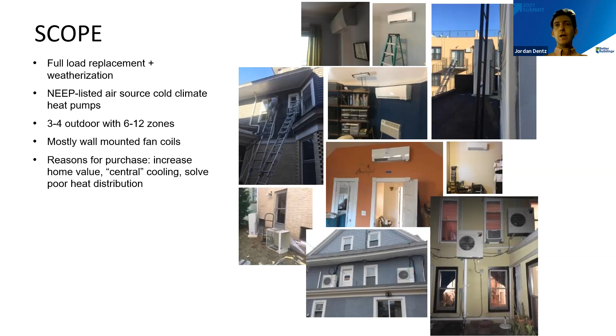One of the things we hoped to gain from this project is what the costs are to retrofit these systems in these types of buildings. Project costs ranged from about $10,000 up to $50,000, with some incentives available for residents. We looked at costs two ways: per zone, meaning per room that received an indoor unit, and per ton of heating capacity. The per-zone cost tends to be more consistent project to project since that's where the labor is—running refrigerant lines, installing and connecting indoor units—less so for equipment size-based costs. We found about $3,500 per zone fairly consistently, and close to $4,500 per ton on average.